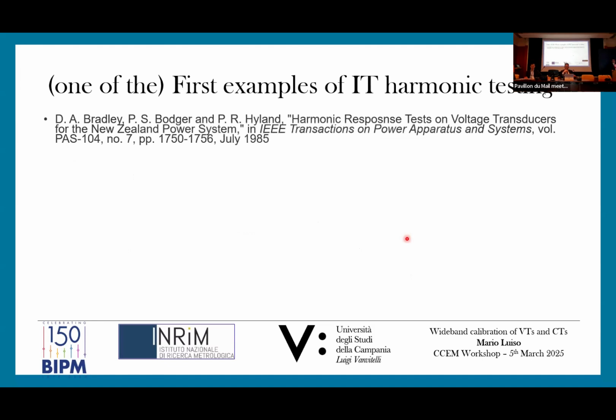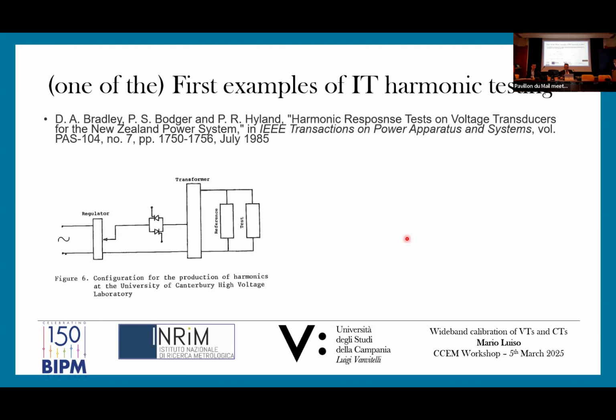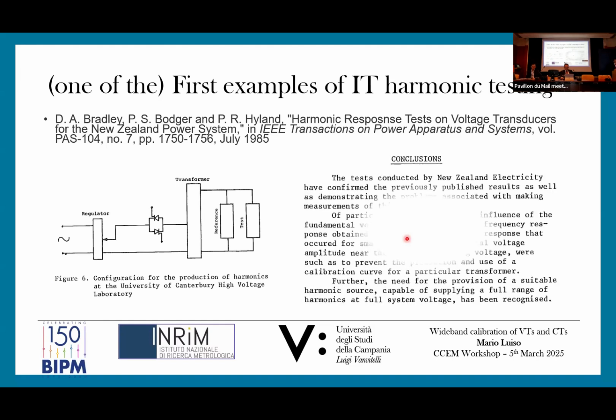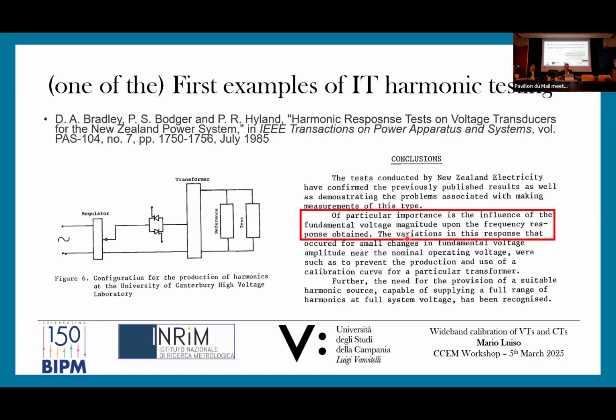One of the first examples of testing instrument transformers for harmonic measurement is about 1985, from people from University of Canterbury in New Zealand. They were doing measurements at high voltage level, and they noticed that the measurement of harmonics with inductive instrument transformers was distorted. So they thought to characterize the instrument transformers with a new kind of setup able to generate harmonics at high voltage level. It is interesting to read the conclusion of the paper now, 40 years ago.